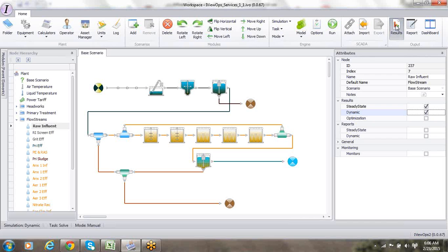And the results will not necessarily look good for ammonia. Our steady state on a 30-day average, or in this case a 15-day average, was saying 0.17. But our results from dynamic simulation, let's look at the flow weighted average, is going to be fairly high. It's going to be around 0.45. So let's look at the results again.